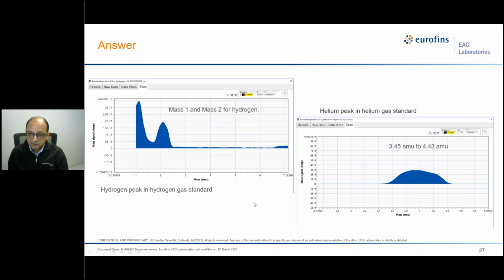So this mass spec has the resolution to differentiate between these two, hydrogen and helium. Now it also depends on the signal strength for helium and hydrogen. If they are very high signals, then it is quite possible that the tail end of the peaks would overlap with each other. But for the range of, let's say, 100 ppm to 20 volume percent, we can resolve between helium and hydrogen. Yes.